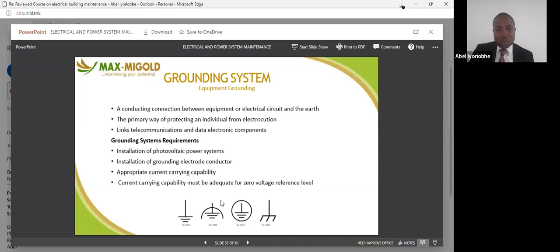So this is what you need to do when you are carrying out tests. Performing ground testing regularly is expected. Considering the soil nature, in the rainy season the earth is a bit loose, so there is free flow of particles, molecules, or ions in the earth. In the dry season, when the whole place is dried up, the earth is a bit caked. What you need to do is test the earth resistivity at regular intervals to know whether your system or installation is at risk or not.